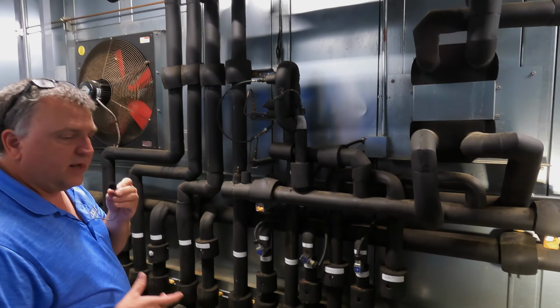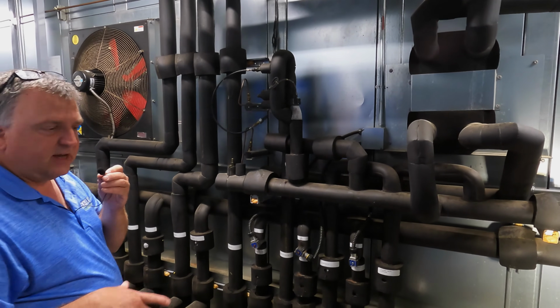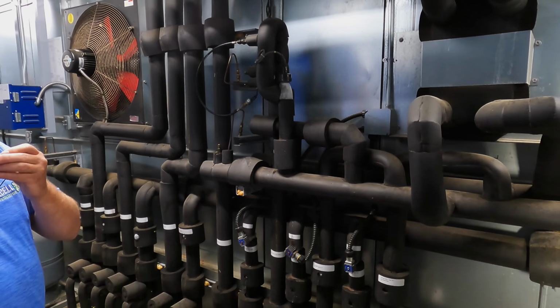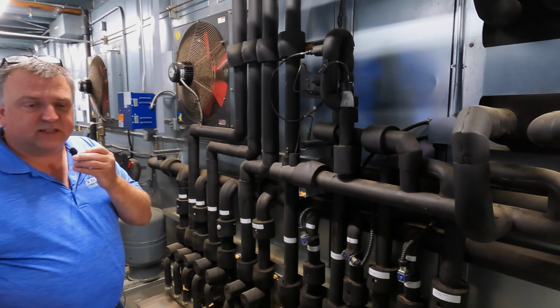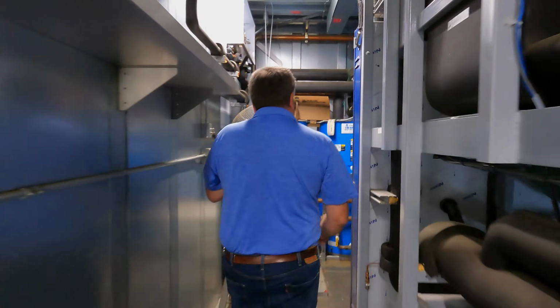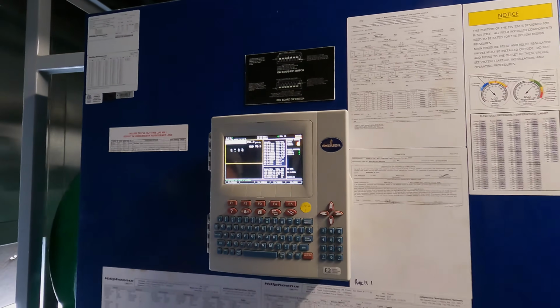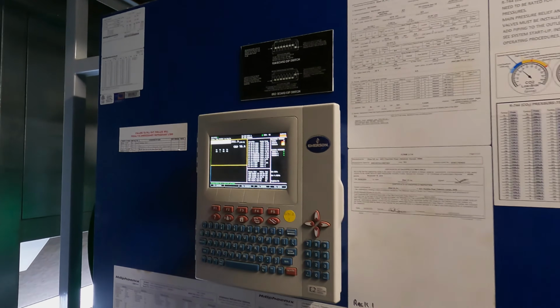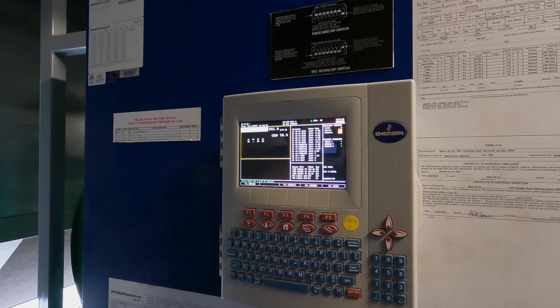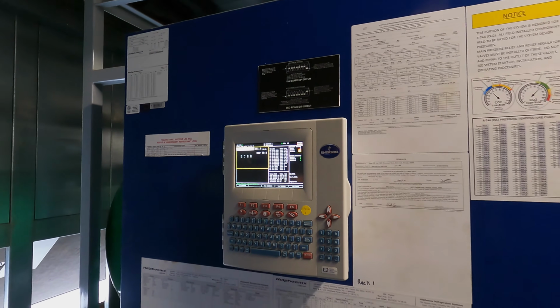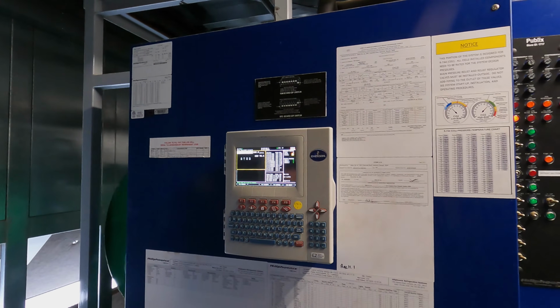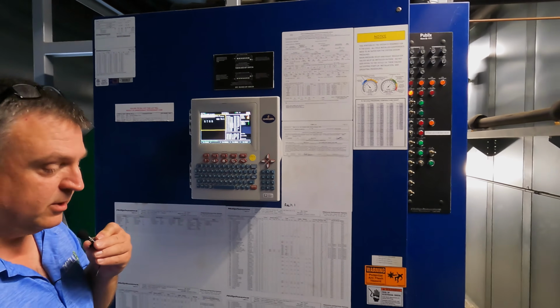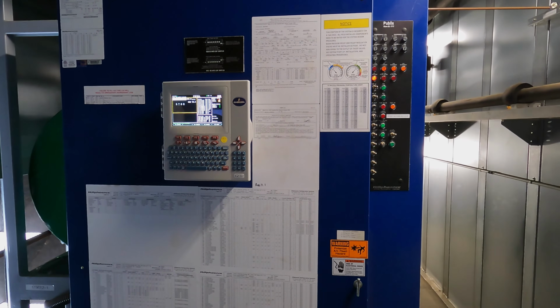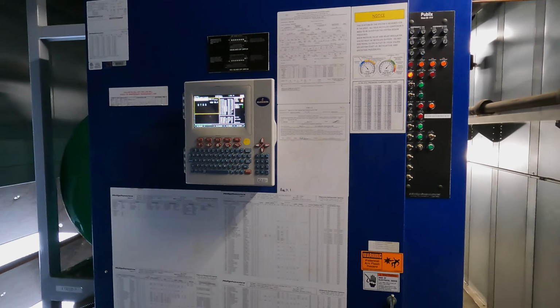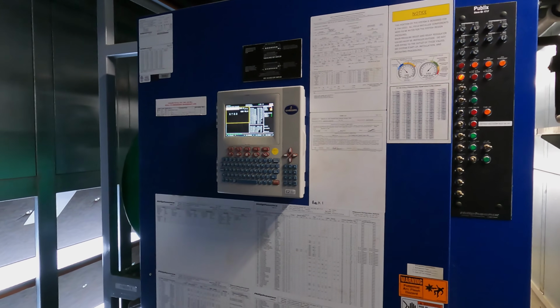Low side's a little bit different. To get the negative 15 degree coil temp, negative 20 sometimes on the cases, we have to use our pressure temperature chart for R744, which is CO2, to get that temperature. Just for reference, on this particular one, we're running 200 pounds of suction pressure in order to achieve a negative 15, negative 20 degree saturation inside of our cases. So in order to do that, we've got to drop the pressure really low, and we're using electronic pulse valves in the case as a metering device going into the coil, which turns the liquid to vapor.